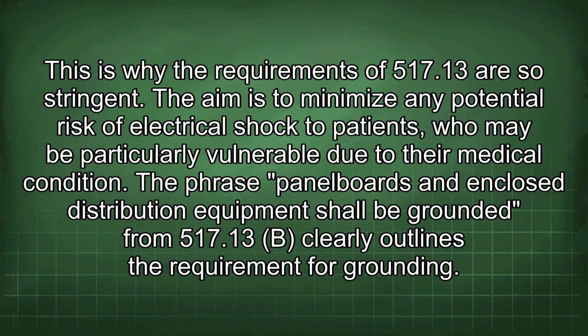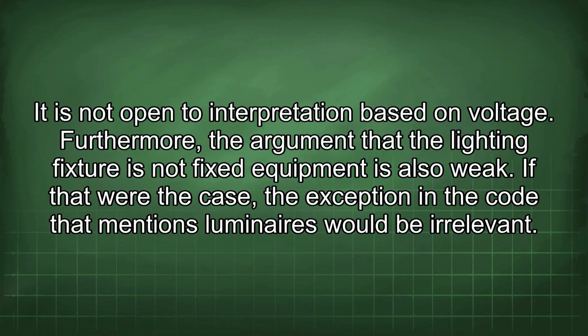This is why the requirements of 517.13 are so stringent. The aim is to minimize any potential risk of electrical shock to patients who may be particularly vulnerable due to their medical condition. The phrase panel boards and enclosed distribution equipment shall be grounded from 517.13b clearly outlines the requirement for grounding. It is not open to interpretation based on voltage.